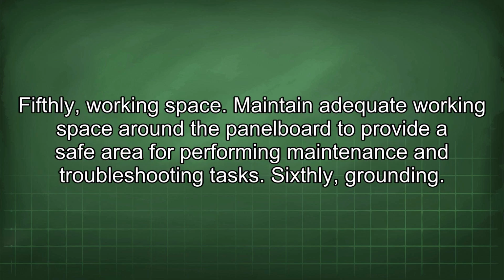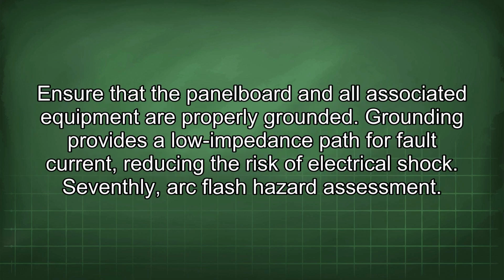Fifthly, working space. Maintain adequate working space around a panel board to provide a safe area for performing maintenance and troubleshooting tasks. Sixthly, grounding. Ensure that the panel board and all associated equipment are properly grounded. Grounding provides a low impedance path for fault current, reducing the risk of electrical shock.